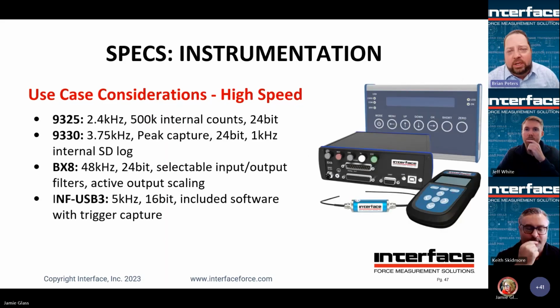So a couple models in the high-speed arena, 9325. That's a portable handheld. It happens to be almost 2.5 kilohertz, 500,000 internal counts, and still 24-bit. So a good high-speed option there. 9330, almost 4 kilohertz sample. Has peak capture as well, 24-bit, so high resolution. It logs to the SD card at 1 kilohertz. That's an example of making sure that you have alignment in terms of what you're looking to do. So if you need to log the data higher than 1 kilohertz, you might need to run it through or pick a different device. BX8, very high speed. That's 48 kilohertz, and that's per channel. These are actually 8-channel devices.